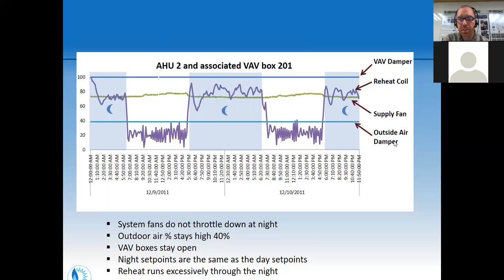Also notice this outdoor air damper is constantly at 40%. This should really be varying - it should at least turn off to 0 at night. During the day, we'd like to see that outdoor air damper vary with the number of people in the building, whether based on carbon dioxide levels or estimates of occupancy, which we actually usually have a pretty good idea of.